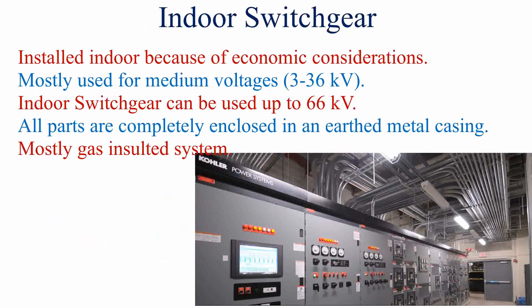Switch gears can be classified as indoor switch gear and outdoor switch gear. Indoor switch gears are installed indoors to reduce installation and operation cost. These are mostly used for medium voltages in the range of 3kV to 36kV, but recently indoor switch gears have been used above this range, up to 66kV.